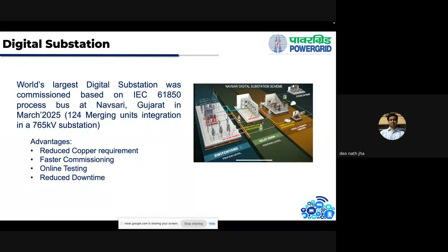So the advantages are reduced copper requirements. In the earlier regime, for each signal you needed one cable. So from a transformer, the temperature reading would flow through one cable, the voltage reading through a different cable, the current reading through another cable. But now all of these are collated within a single fiber optic cable, which runs from all the equipments, a single cable collecting data from all the equipments in a substation. That single cable carries all this data to the relay panels, and it enables faster commissioning of assets and online testing.